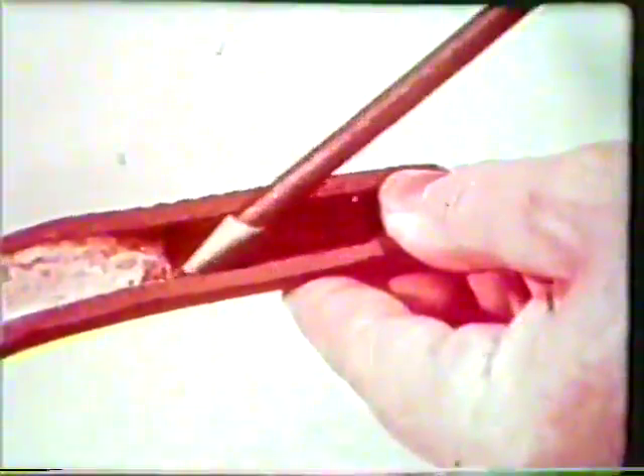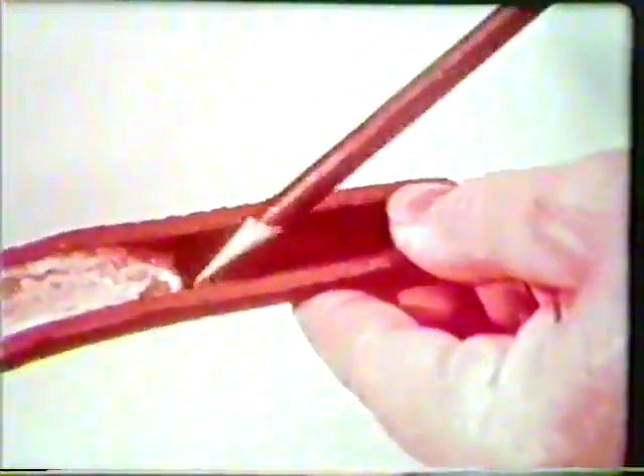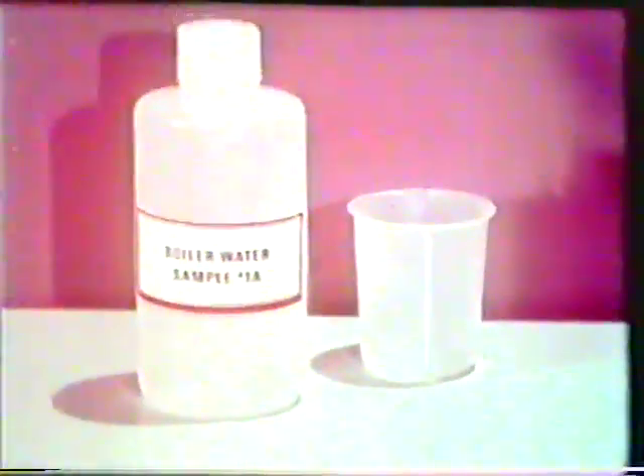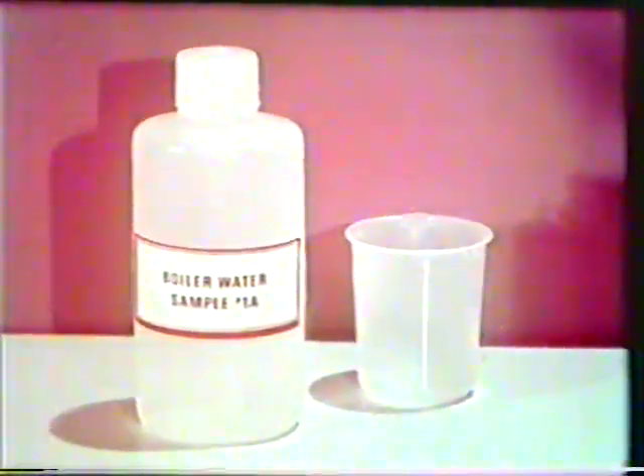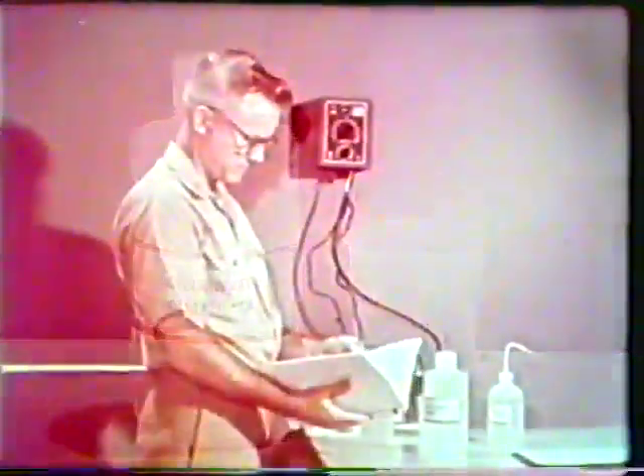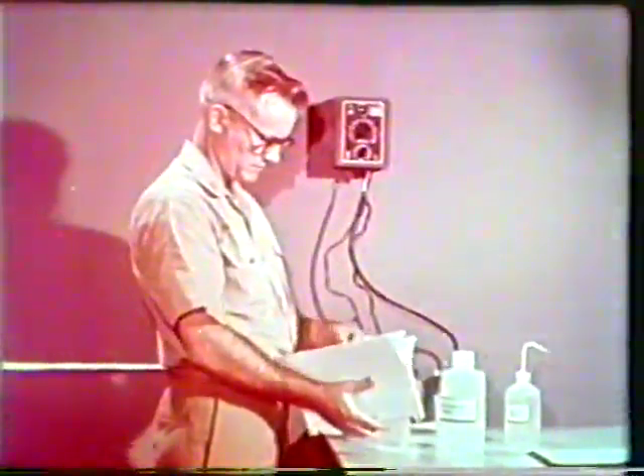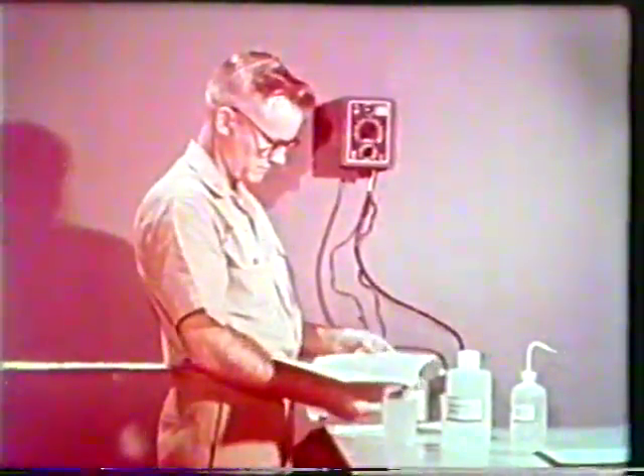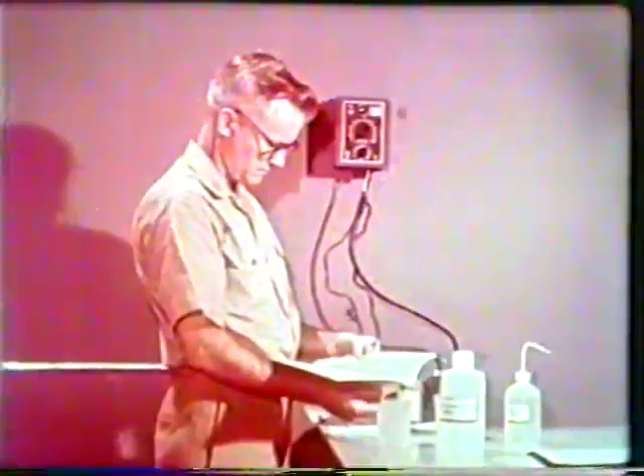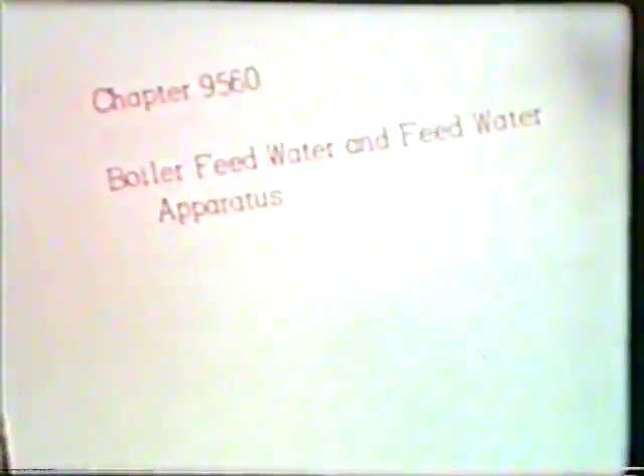To prevent this, the dissolved solids must be controlled. A direct relationship exists between the amount of dissolved solids and the electrical conductivity of boiler water. Therefore, conductivity values can be used to determine if boiler water contains an excessive amount of dissolved solids and if corrective action is required. Boiler water must be tested periodically as scheduled in NAVship's Technical Manual, Chapter 9560.